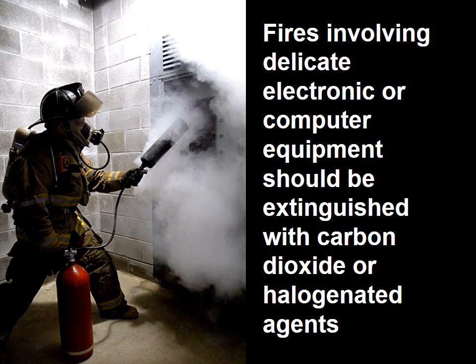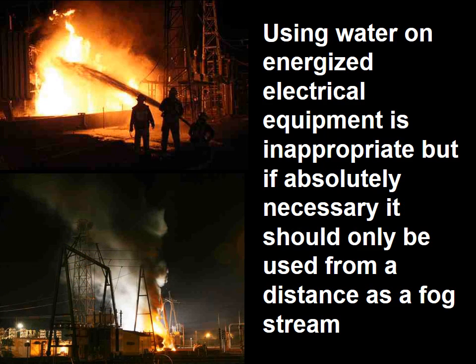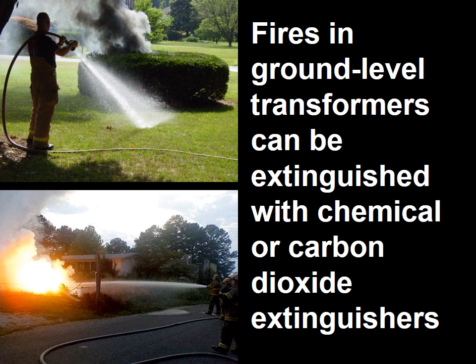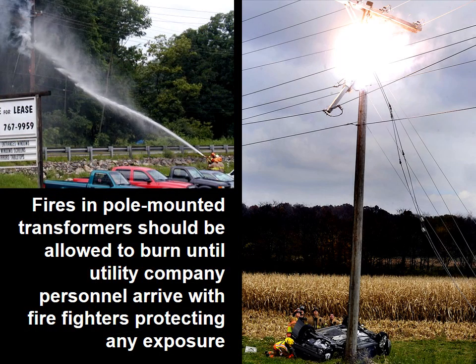Fires involving delicate electronic equipment or computer equipment should be extinguished with a carbon dioxide or halogenated agent. Using water on energized electrical equipment is inappropriate, but if absolutely necessary, it should only be used from a distance as a fog stream. Fires in ground-level transformers can be extinguished with a chemical or carbon dioxide extinguisher. Fires in pole-mounted transformers should be allowed to burn until the utility company personnel arrive, with firefighters protecting any exposures.